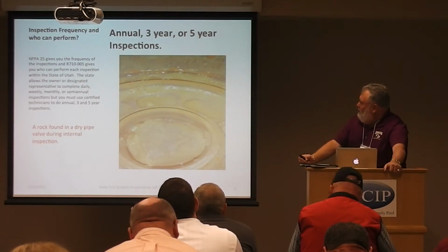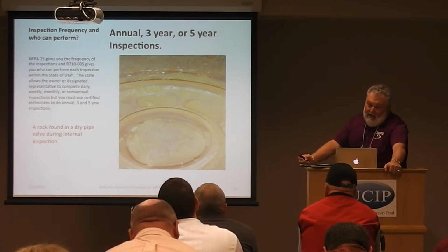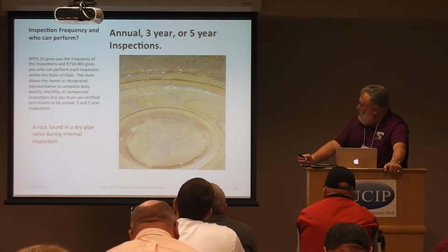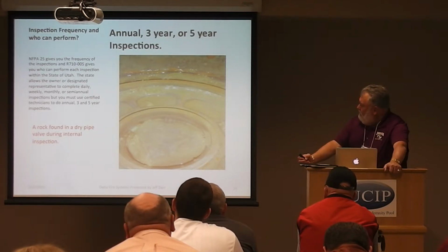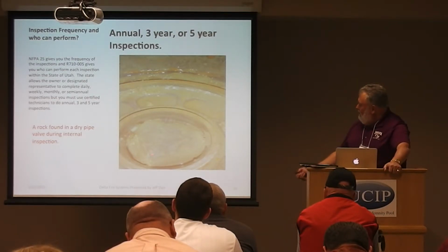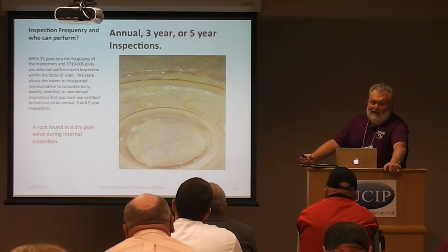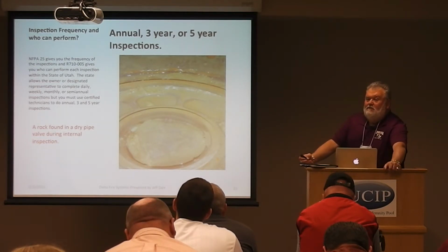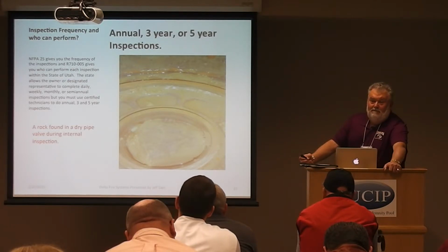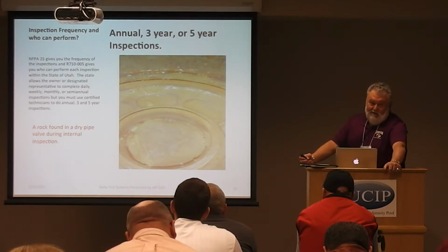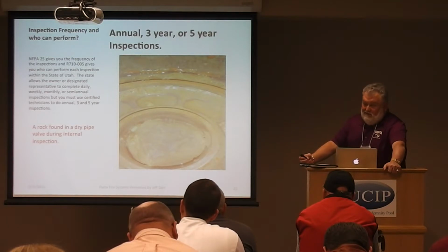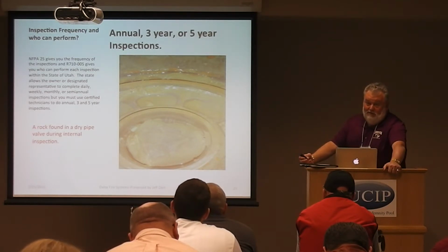Okay, annual, 3-year and 5-year inspections have to be done by a certified technician. This was a rock we found in the dry pipe valve during the internal inspection. I'm just amazed at how close that rock fits right in there. Could anybody tell me, could a tech level 1 do this internal inspection? The answer is no. It would have to be a tech level 2 because it's a dry system. If you had a tech level 1 saying he's doing an inspection on a dry system, he's exceeding his authority by state rule.